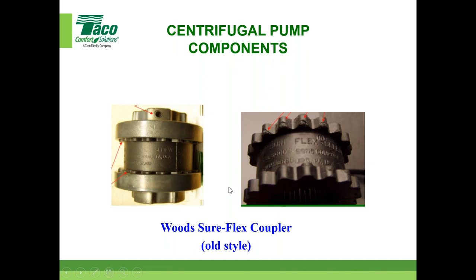Here's the old style. I call it the old style. It's still out there. The Sureflex coupler. And this is the arrangement here. When I first started, that was our standard. But more and more pumps had drives added to them, and we were finding that this material wasn't holding up well to the starting and stopping and the speeding up and slowing down. In many applications, all of a sudden, this black dust would show up on the base. And once the teeth start going away, then the coupling's no good and it had to be replaced.